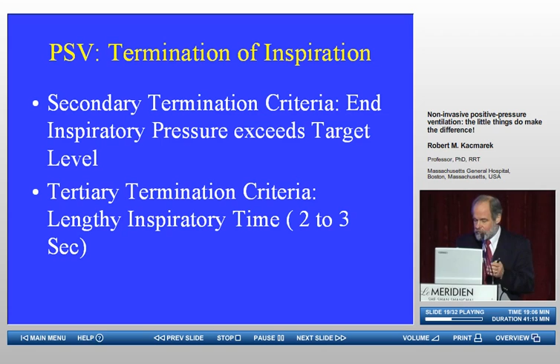Just to be complete, there is a third level, and it's a lengthy inspiratory time, 2 to 3 seconds in some ventilators. Now, one of the things I did not mention: with some of the non-invasive ventilation packages on ICU ventilators, they do allow you to set a maximum inspiratory time during pressure support, which is clearly a very useful adjunct for the patient who is being non-invasively ventilated. So you can either end the breath when flow decreases to the predetermined flow rate, or when inspiratory time hits that setting. What I usually instruct my staff is to set that inspiratory time at about 1 second, so that if the patient doesn't cycle off with a diminished flow, at least after a second there'll be a transition to the expiratory phase.